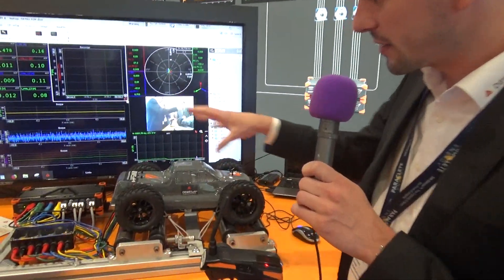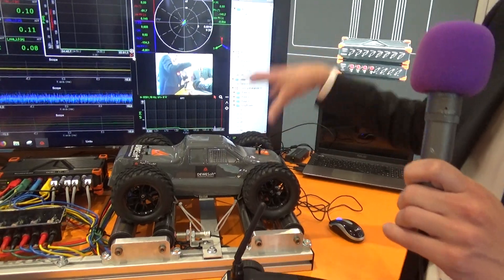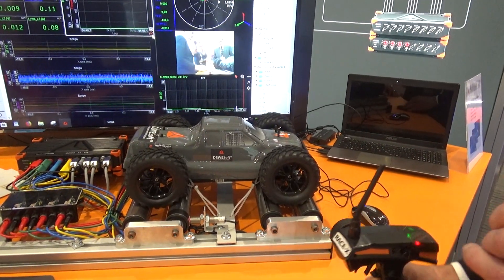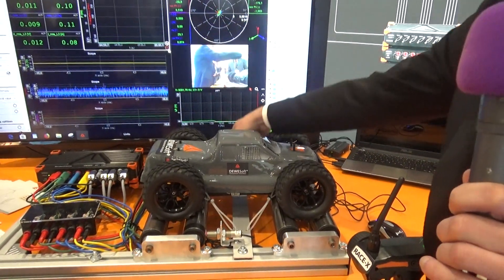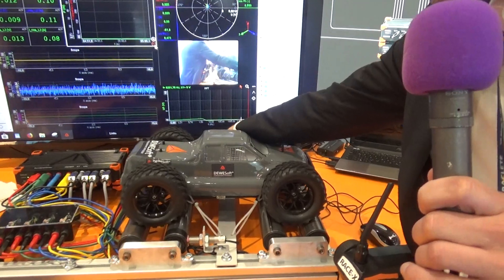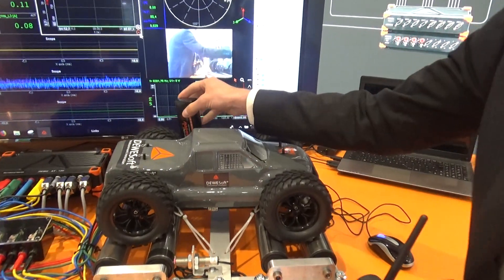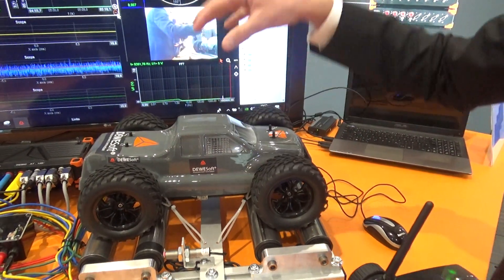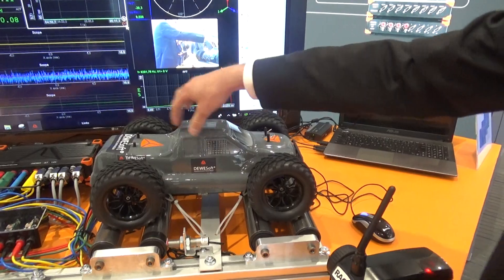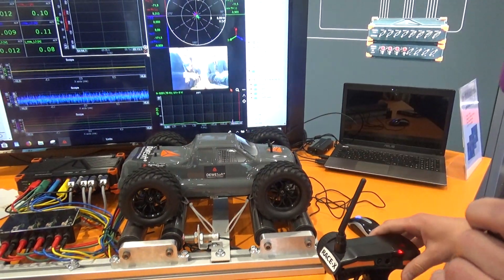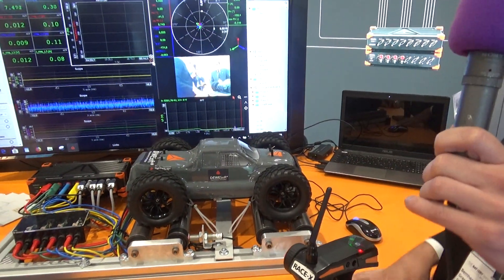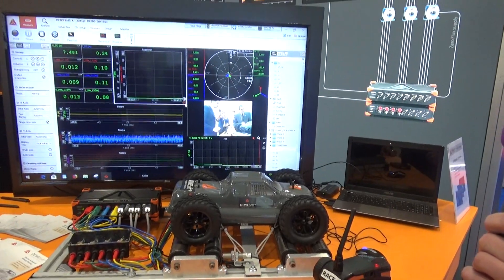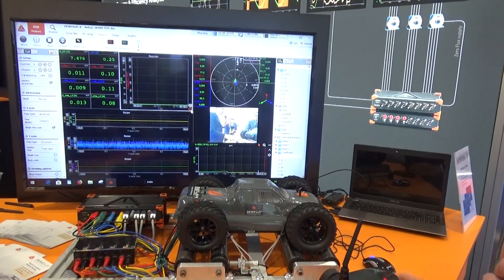Here we connected our power analyzer to a remote control electric vehicle. We have a small battery, and here we do the DC power analysis. Then inside we have an inverter, and then a three-phase AC motor, and here we do the three-phase AC power analysis.